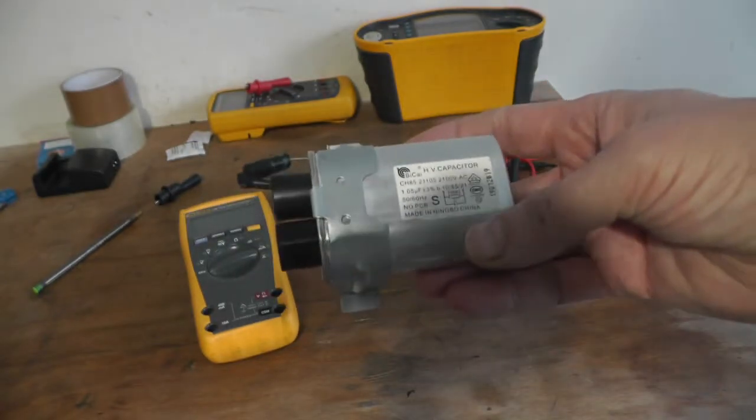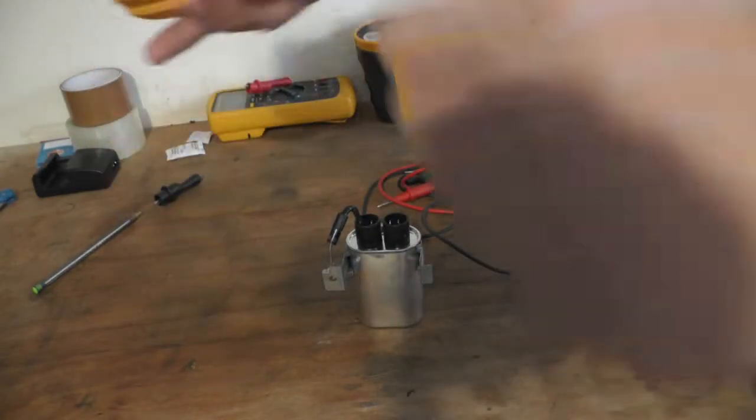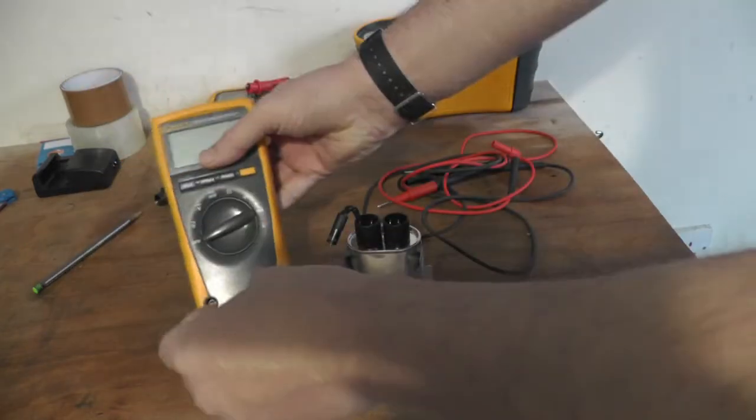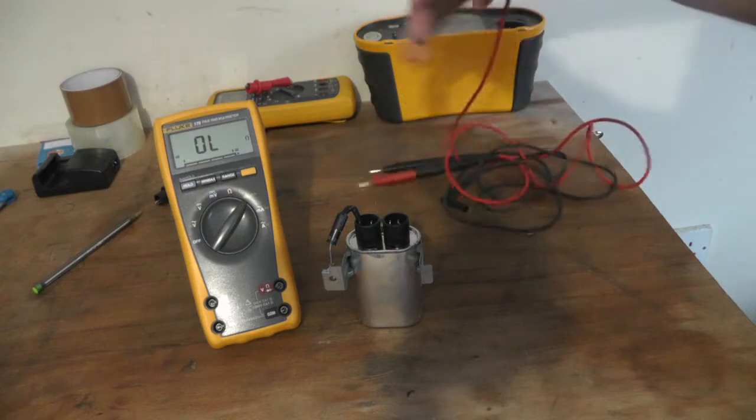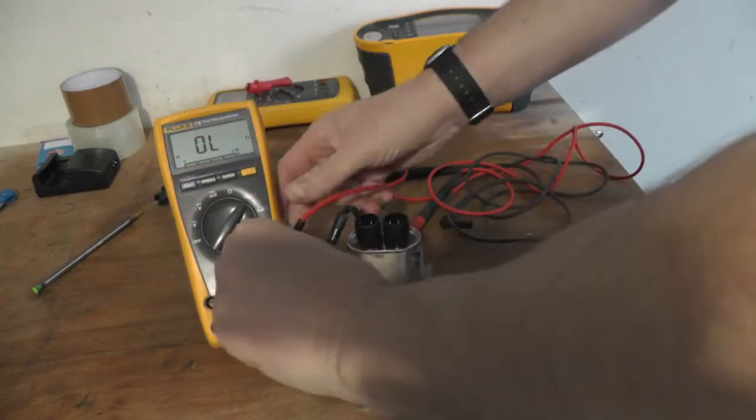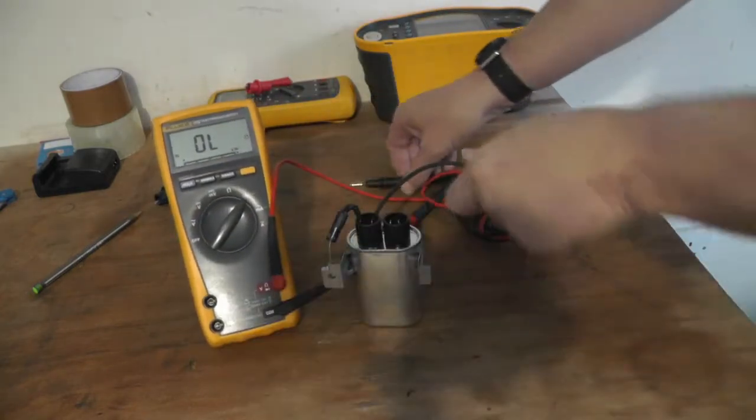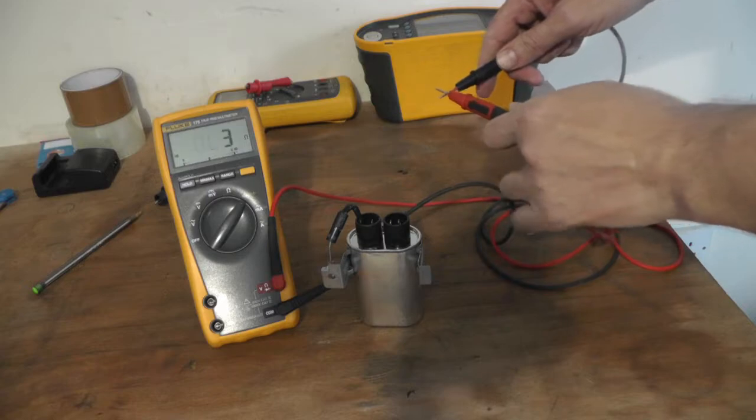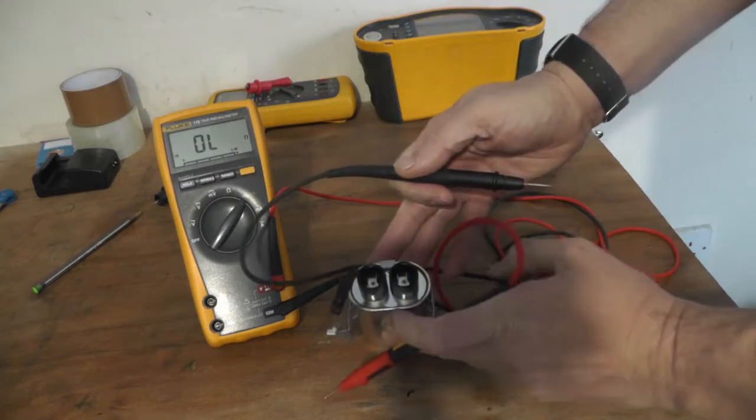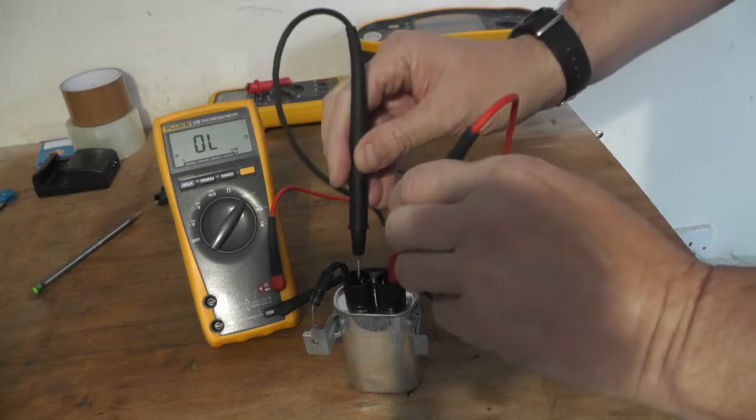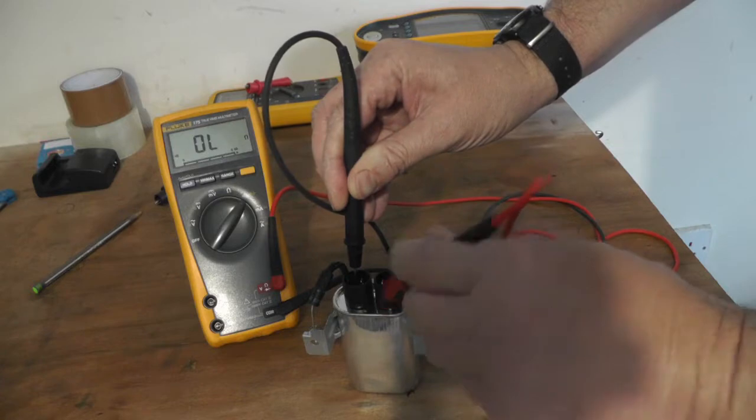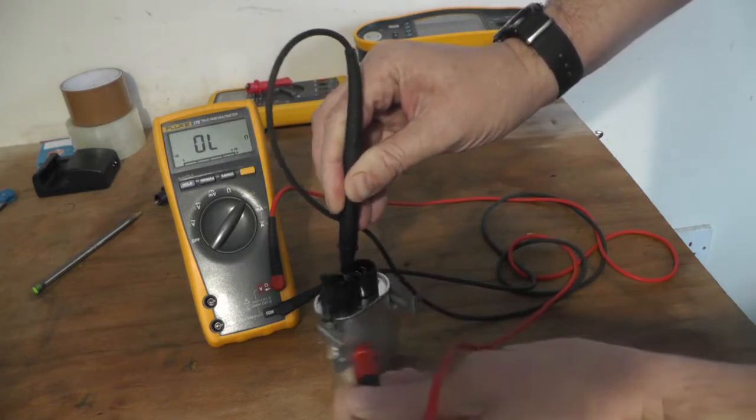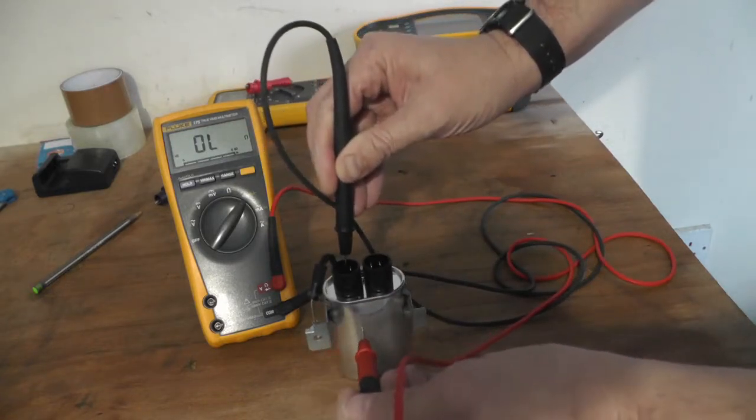So I'm going to test it first on continuity. Set the continuity on the buzzer, make sure it works, then test between each of the two terminals on the top. You should be getting nothing, and nothing to earth neither, or nothing to the body of the unit. If there's any leakage, then it's faulty.